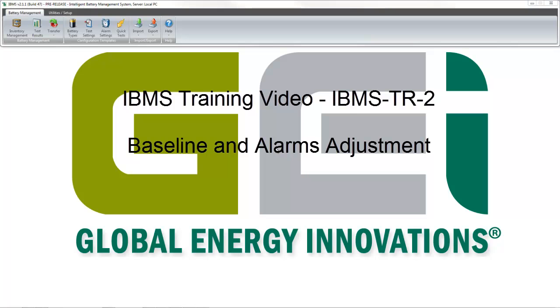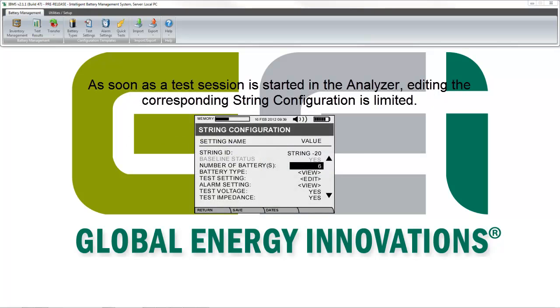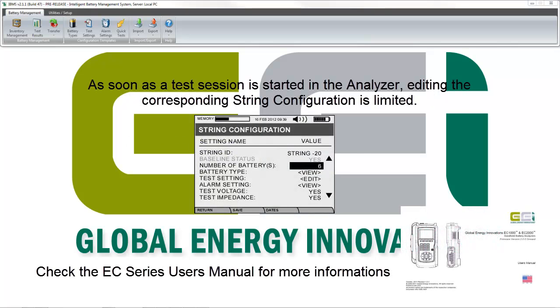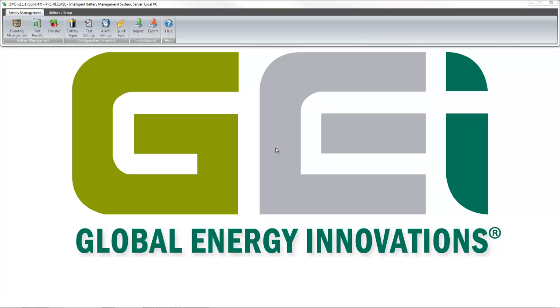This training video reviews the procedure for adjusting baseline and alarms in IBMS. Once a test session has been initiated on the analyzer, it is impossible on the analyzer to modify alarm levels or population reference baseline values. Such modifications can be done in IBMS.